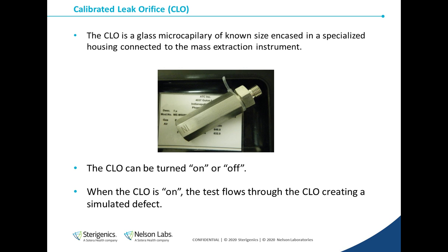It's a defect of known size that's incorporated into the instrument. There's a switch on the instrument that turns the CLO on or off. When the CLO switch is off, the CLO path is closed. When the CLO switch is on, the test goes through the CLO, so the result is equivalent to having a 2 or a 5 micron defect in the sample.